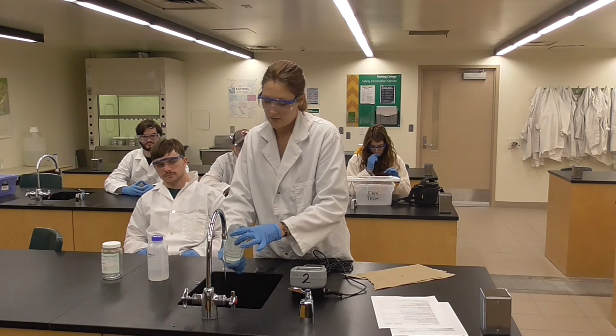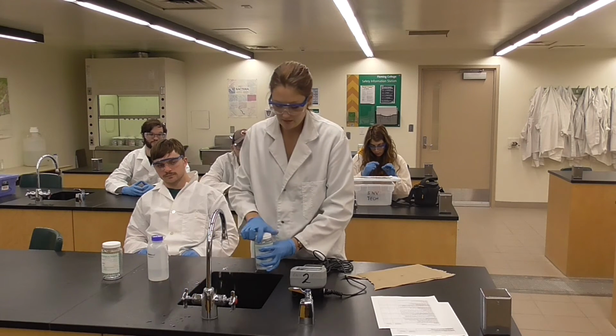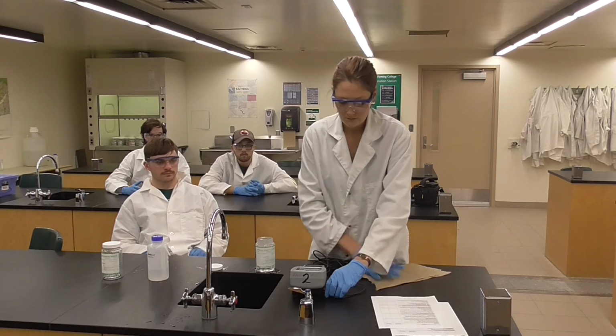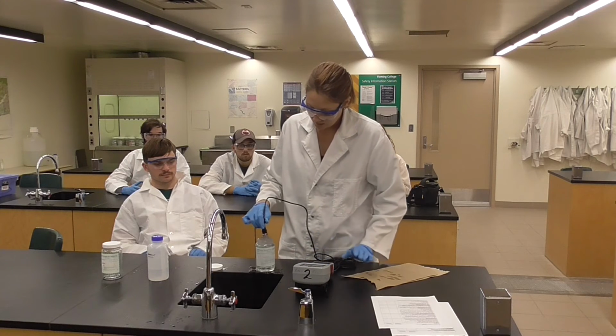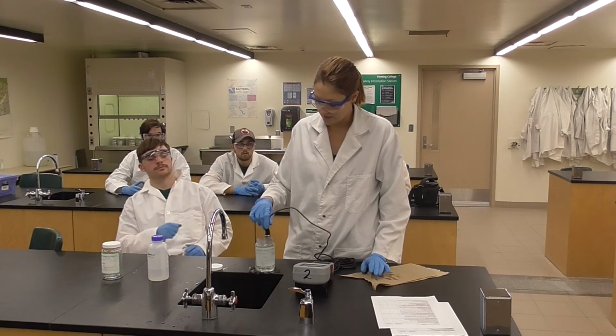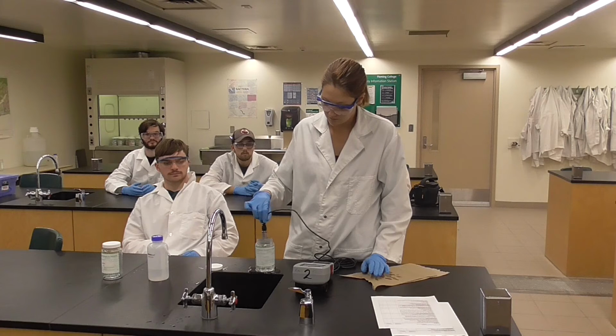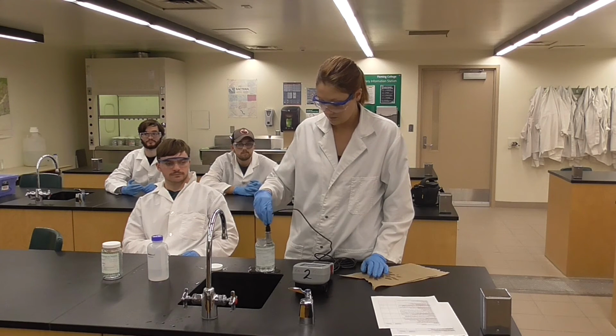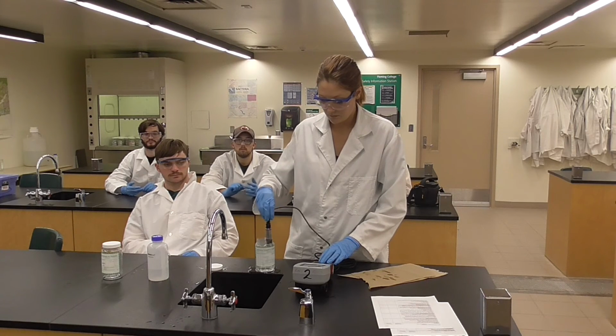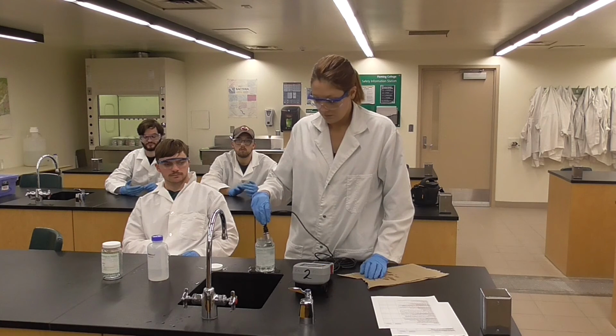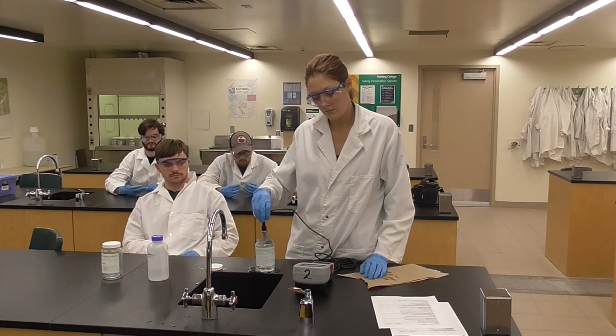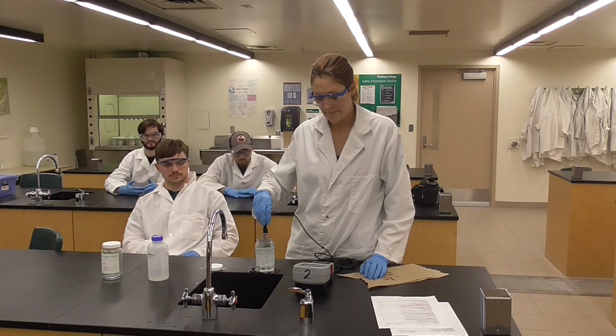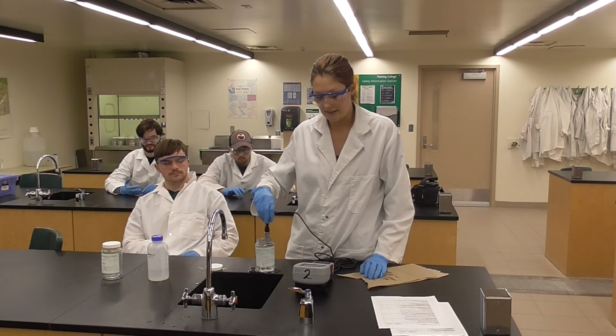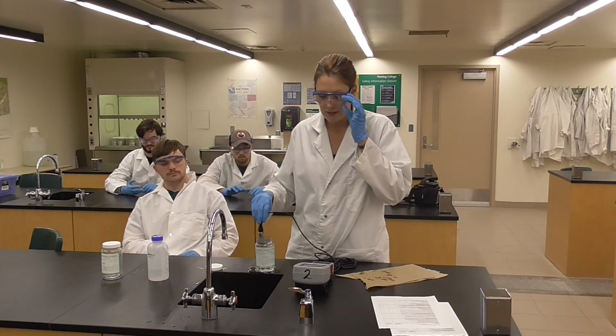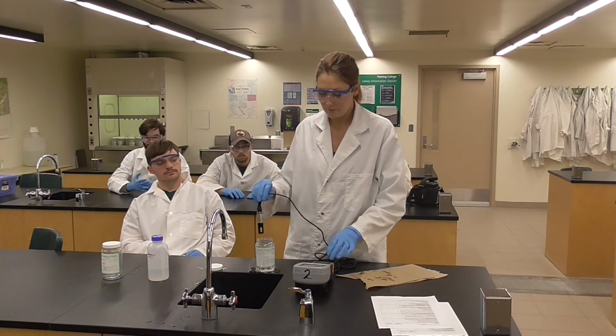Okay. So if you're taking this elsewhere, we want the 0 headspace on here, but I'm testing it right now. And once again, it's at the 16 centimeters per second rotation rate. Alright, and so this sample has stabilized out at 11.68 milligrams per liter of dissolved oxygen and a temperature of 18.7 degrees Celsius. So now we're done.